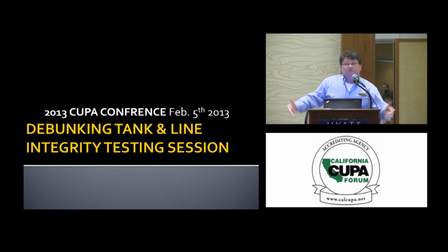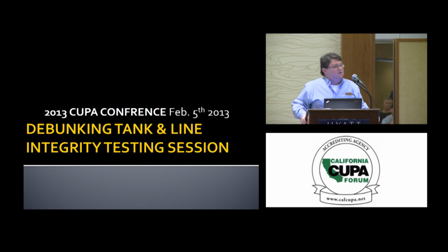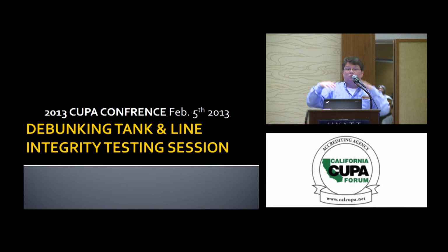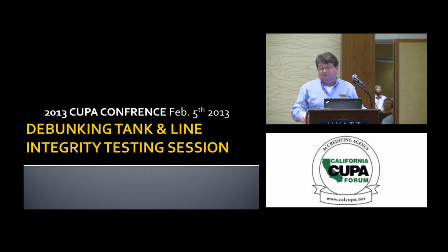Not everybody does. You've probably witnessed someone that you went, boy, I don't know if that guy really knows what he's doing or not. That's why it's important you know what's going on. You know the parameters of how they test. How does groundwater affect the test? Well, if it's an equilibrium state, you might have just enough pressure coming in to mask a leak. If it's not, you may have to raise the level of the fluid or lower the level of fluid to determine that there is a leak or not a leak.